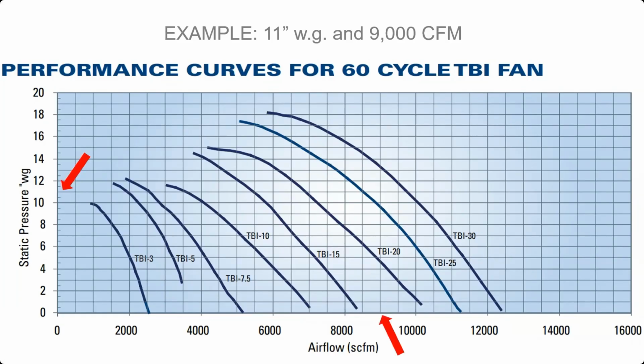And when those lines up, we land actually between 2 sizes, the TBI 25 or torque backward incline and the TBI 30. When the lines intersect in between 2 fan curves, like they do here, we generally select the larger size fan since you can always damper that back. So in this case, I would select the TBI 30.